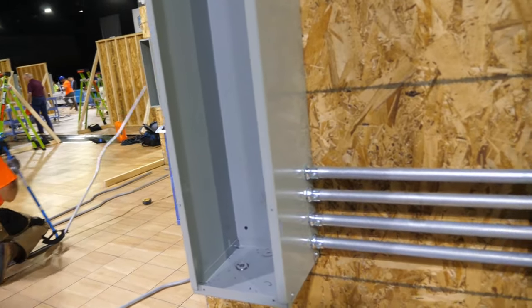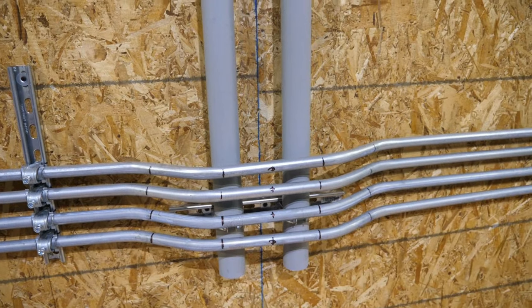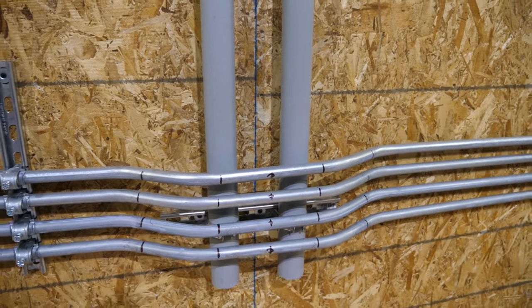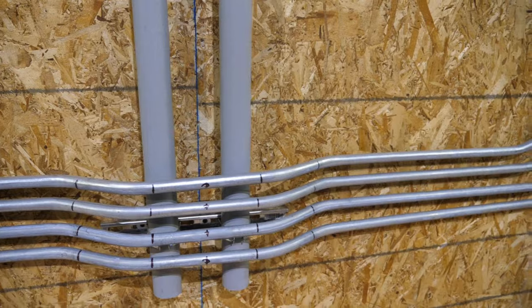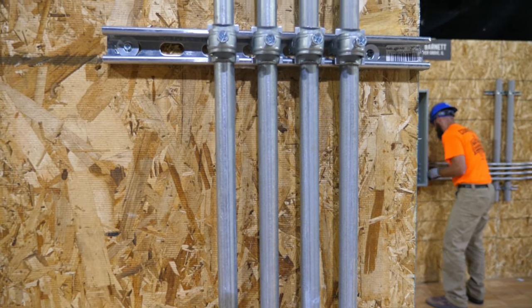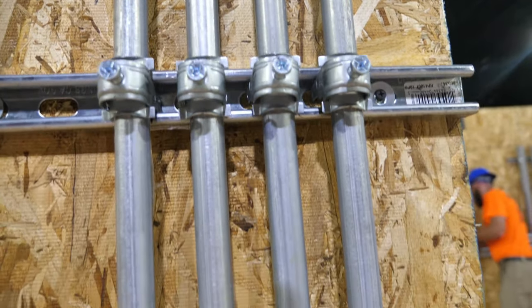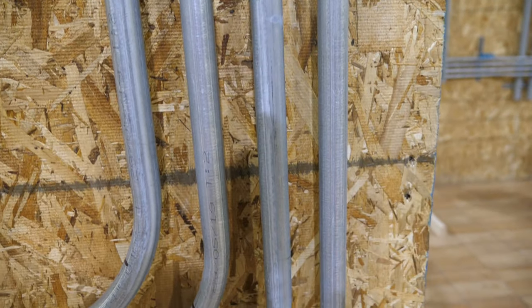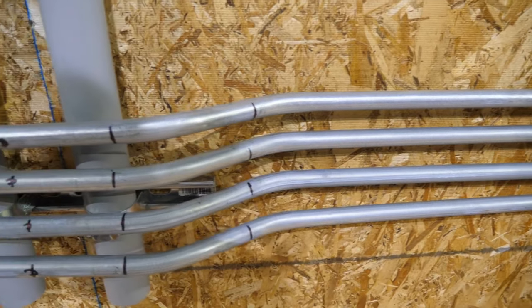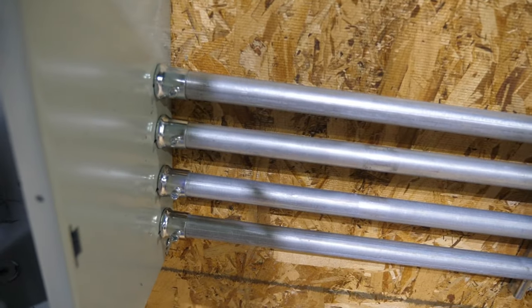Now it's time for judging by you the viewers. Please subtract three minutes from the time of both Greg and Michael in relation to Sparky, because Sparky didn't have to put the fittings on the boxes. Remember, time accounts for 10% of the total score. Here's Greg's work — you see very nice bends, well strapped, going to the box. Good distance between the pipes, and here's the four-point saddle band jumping over the obstacles, with more straps going back to the box.